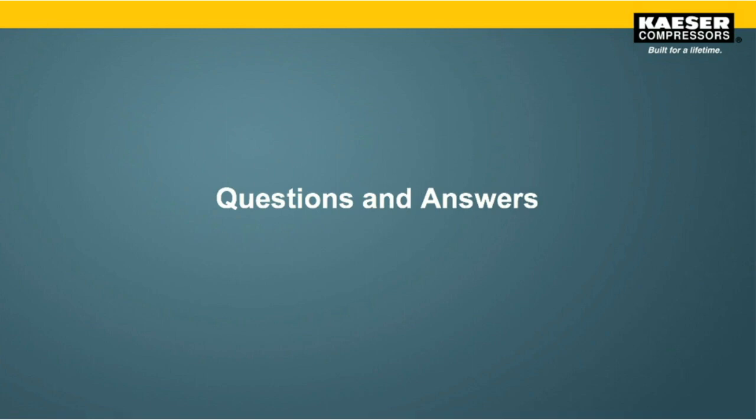Yeah, so this is Grayson again. Really, you've got to look at the system as a whole. If you're having multiple fixed speed machines loading and unloading at the same time, or you've got a variable speed compressor that's ramping up and ramping down at the same time that a load-unload machine is starting and stopping, that's a good chance that there's some kind of control issue.